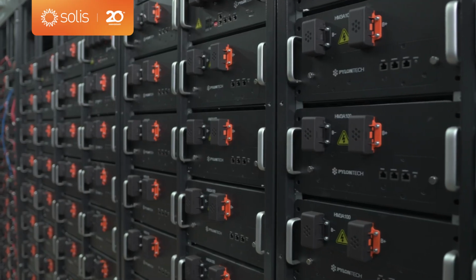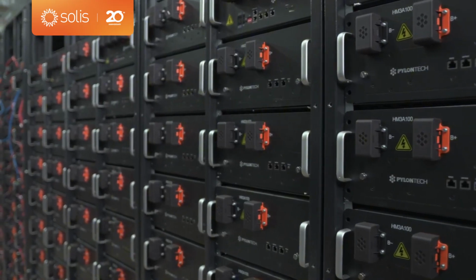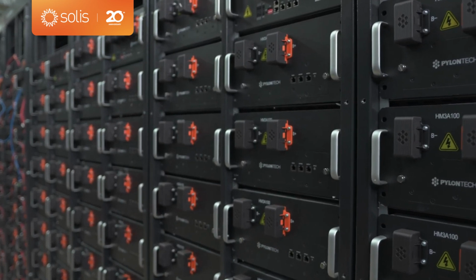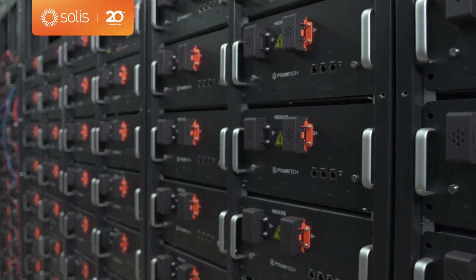Now, battery compatibility, that's really important. What batteries does it work with? Well, performance is really important when it comes to batteries, and the inverter works with high voltage lithium batteries. So we've connected it to 8 stacks of 17 Pylontech power cubes, and that gives us something close to 800 kilowatt hours of storage. We haven't quite fully built it out yet. We're around the 400 mark at the moment, but that's plenty of storage. And we're running up around 700 volts, which is just perfect for a 3-phase inverter, though it'll accept voltages from 150 all the way up to 800 volts.